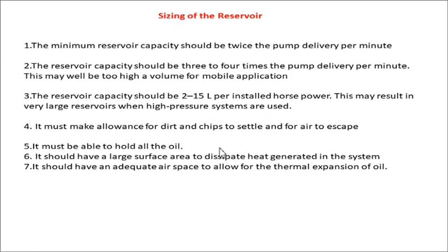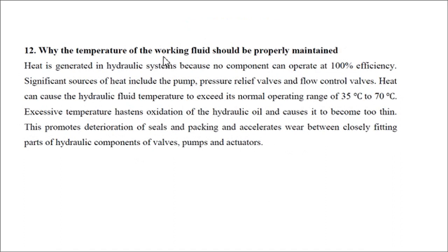It must be able to hold the oil, it should have a large surface area to dissipate the heat generated, and it should have adequate airspace to allow for thermal expansion of the oil. Why should the temperature of the working fluid be properly maintained? Because heat is generated in the hydraulic system, as no component can operate at 100% efficiency.